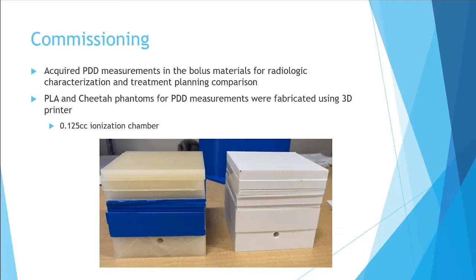The way we did this is we had the slab at the bottom. We designed an insert to fit a 0.125 cc ionization chamber that we had. And then we printed slabs of varying thicknesses that we could place in different orientations on top of the slab. By doing this, we could obtain ionization readings at discrete measurement points throughout the depth ionization curve, and that would allow us to construct a complete percent depth dose curve.